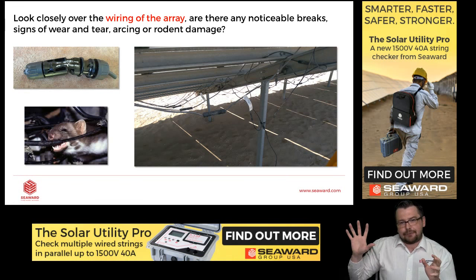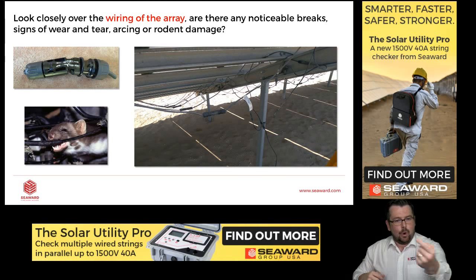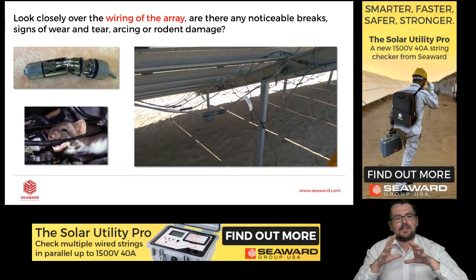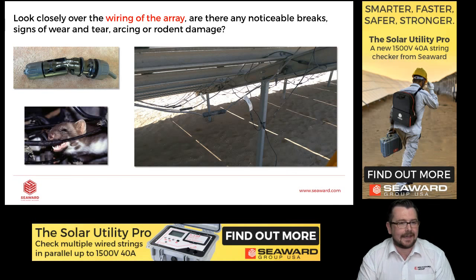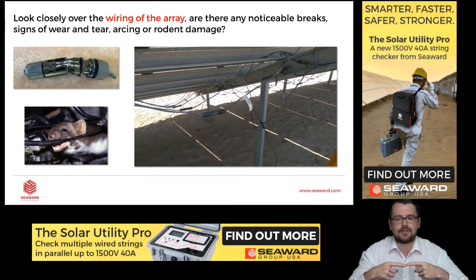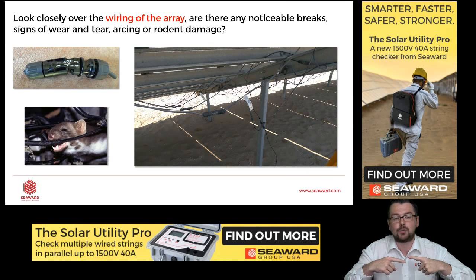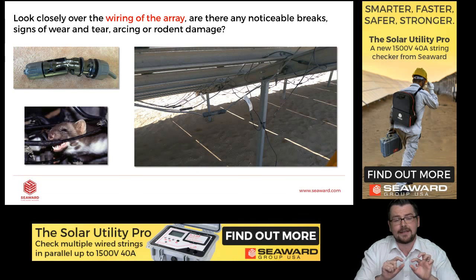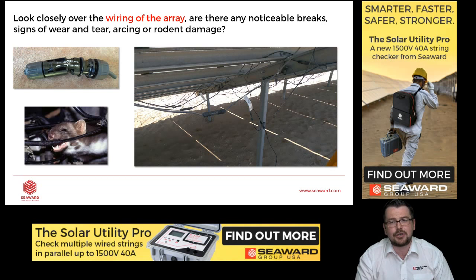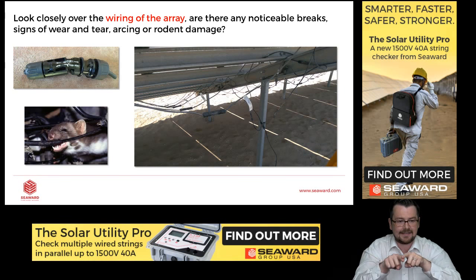So once we've had a look at the front of the array, I would then take the walk back along the back side of the array. And at this point, what we want to look at is the cabling in particular, because this is where the major problems I find, and the majority of the problems I find on solar PV farms, particularly the MC4 connections. If they're not made correctly, or if there is dust in the MC4 connections when they're made, this can cause arc faults inside of the connection, and you can see that on the image on the top left hand of the screen.